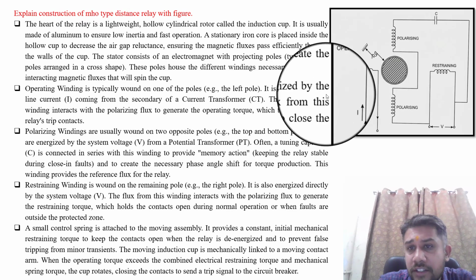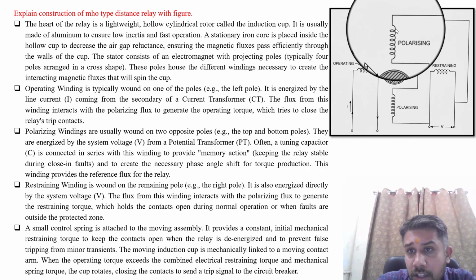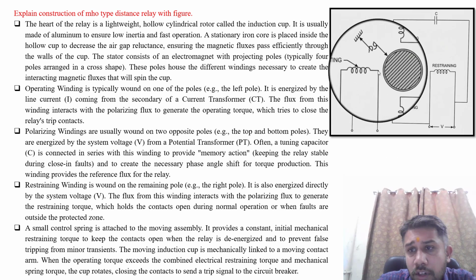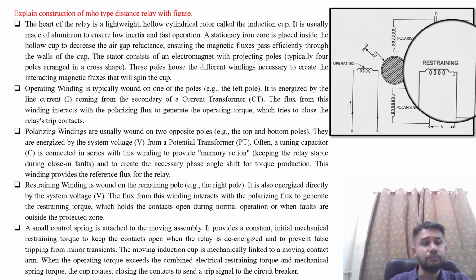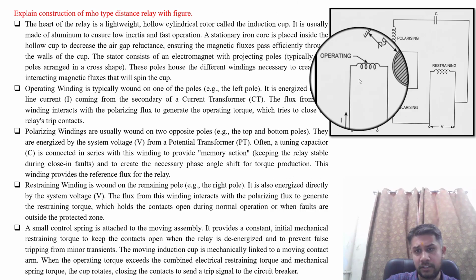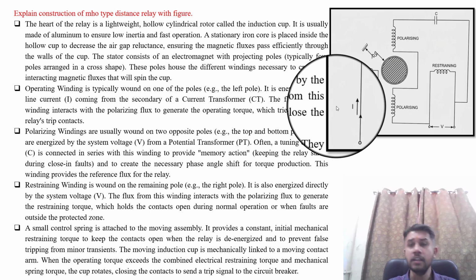So here you can visualize these are the 4 poles. These are 2 poles, this is 1 pole and this is another pole. Now these 4 poles have windings over them, which are made of copper. The operating winding is typically wound on one of the poles, that is the left side pole here. It is energized by the line current which is coming from the secondary of the current transformer, CT.